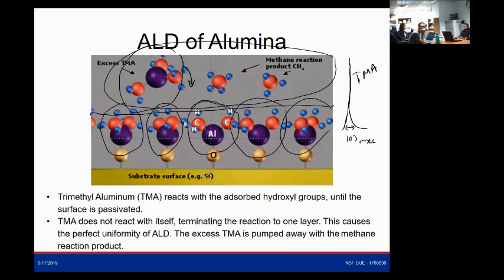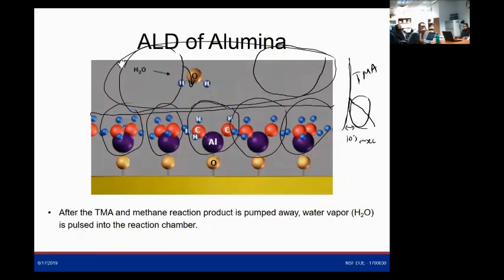Okay, so first, since methane will be released, you will see that this pulse will be enlarged because now there's going to be a detected methane gas release in your gauge. Does that make sense? So it will not be a sharp pulse on your gauge reading. It will be a lengthier pulse.